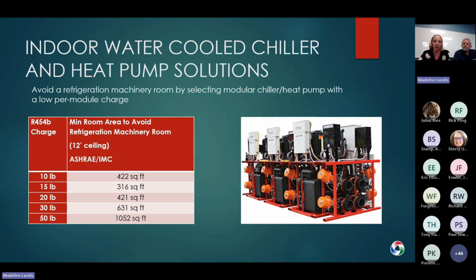The interesting and cool thing is that Multistack actually just released a new technology, and it's called their microcharge module. With this design, they have modules that have as low as 0.6 pounds of refrigerant per ton. So it's a really cool way to be able to fit modules into those spaces.